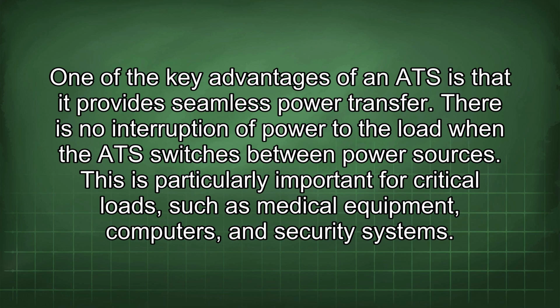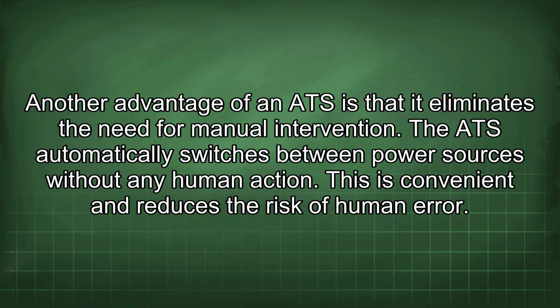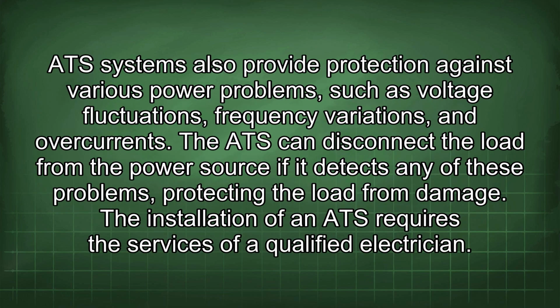This is particularly important for critical loads, such as medical equipment, computers, and security systems. Another advantage of an ATS is that it eliminates the need for manual intervention. The ATS automatically switches between power sources without any human action. This is convenient and reduces the risk of human error. ATS systems also provide protection against various power problems such as voltage fluctuations, frequency variations, and overcurrents. The ATS can disconnect the load from the power source if it detects any of these problems, protecting the load from damage.